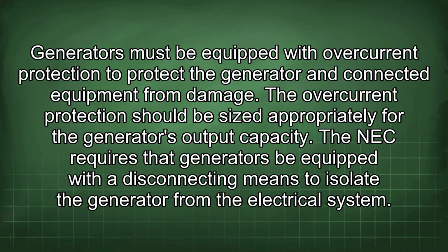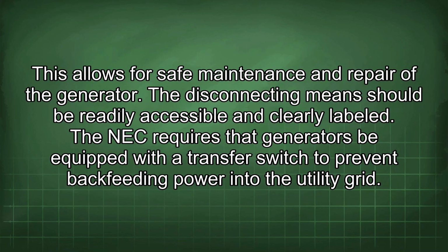Generators must be equipped with overcurrent protection to protect the generator and connected equipment from damage. The overcurrent protection should be sized appropriately for the generator's output capacity. The NEC requires that generators be equipped with a disconnecting means to isolate the generator from the electrical system. This allows for safe maintenance and repair of the generator. The disconnecting means should be readily accessible and clearly labeled.